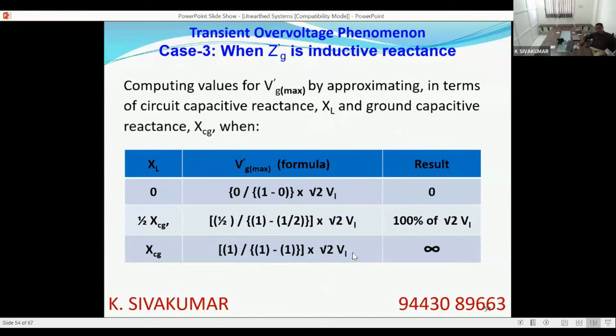Now if you see, 0 means 0. If the external impedance or inductive reactance is 50% of the capacitive reactance of the leakage network, you see 100% root 2 VI is introduced. If the external impedance is 100% of the leakage capacitance, so XL equal to XC, whenever XL equals XC, it is called resonance. You can see the voltage is almost infinity. It is not practically infinity because the network also contains some resistance. The resistance reduces it to an extent, but it is very high.